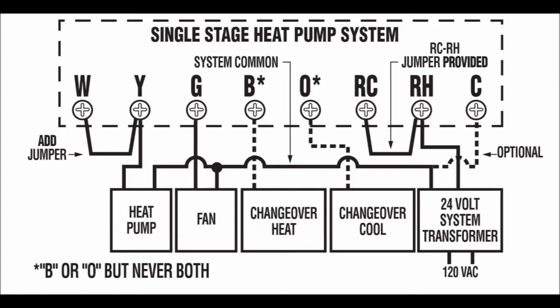It turns on the compressor during cooling, but for heating, the W originally would have turned on the furnace, but now it also has to turn on the heat pump because the compressor also gets used for heating as well. So this is the setup. So basically all the control wires, yellow to yellow, black to black, red to red, white to white, and blue to blue all land on that terminal strip.